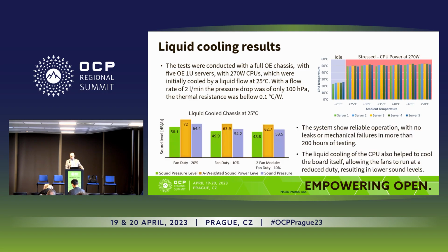Then the second key finding I can show here is that with liquid cooling we can reduce very significantly the fan speeds for the DRAMs and SSDs, which are still air-cooled, and you can see that it's about a 10 decibel decrease in acoustic noise in the system.